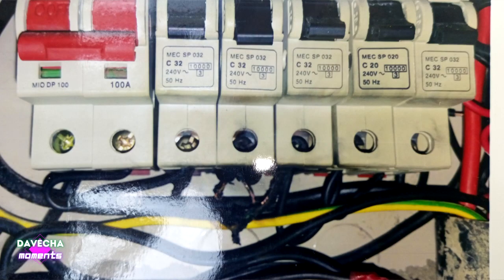Number one, the picture that you see shows the effect of heat on the fourth circuit breaker from your right. You will see that the circuit breaker at the bottom is dark. The wire is burned. There is a loose connection in that wire. This has been caused by loose connection. Okay, you can see it has picked on a circuit breaker. There are 1, 2, 3, 4, 5 from the right, and then the double pole.